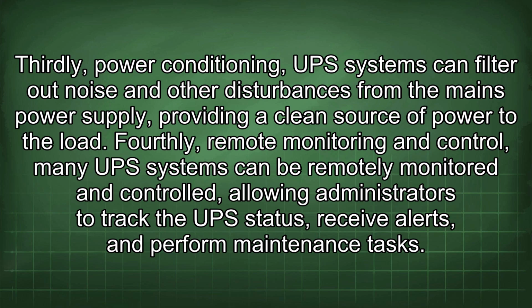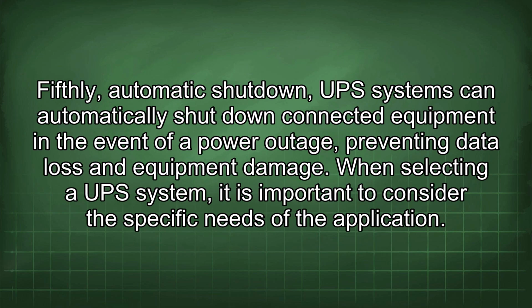Fourthly, remote monitoring and control. Many UPS systems can be remotely monitored and controlled, allowing administrators to track the UPS status, receive alerts, and perform maintenance tasks. Fifthly, automatic shutdown. UPS systems can automatically shut down connected equipment in the event of a power outage, preventing data loss and equipment damage. When selecting a UPS system, it is important to consider the specific needs of the application.